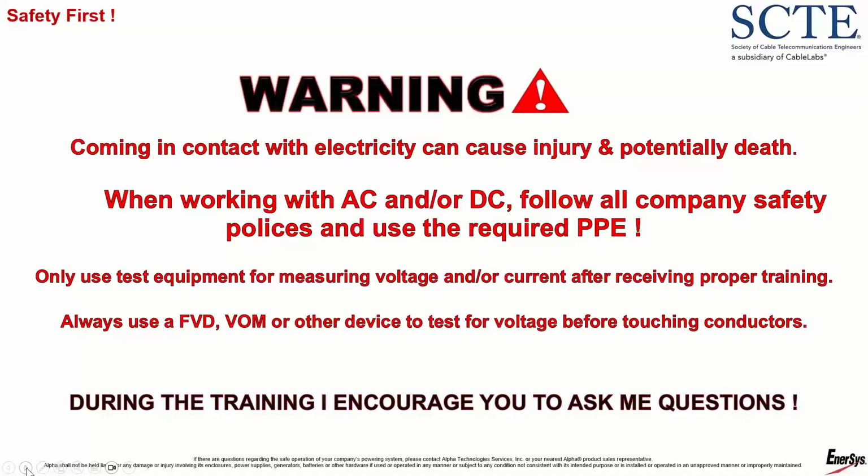There are a lot of conductors out there that are not supposed to be energized, but there is a potential that they can be energized. So use a foreign voltage detector, use a voltmeter, wear your gloves, use devices to test for that foreign voltage. Don't be using your body to find out if it's hot or not.